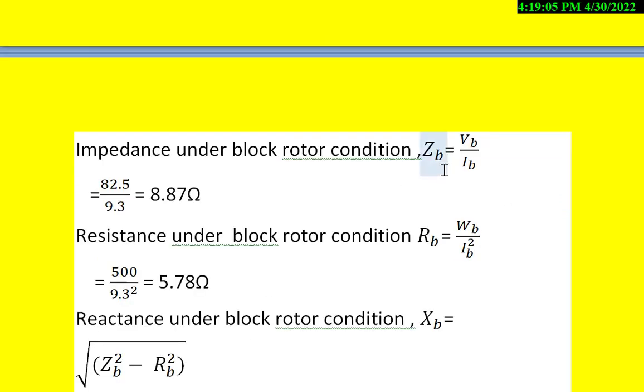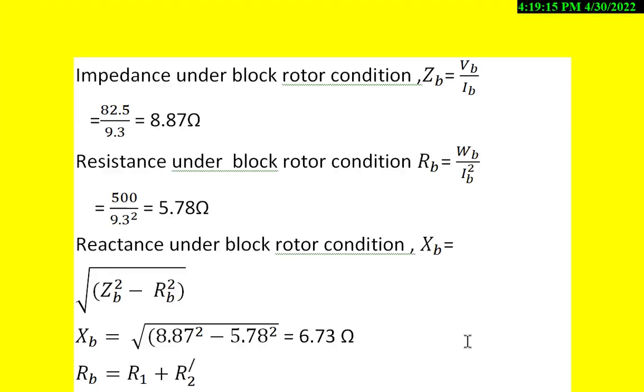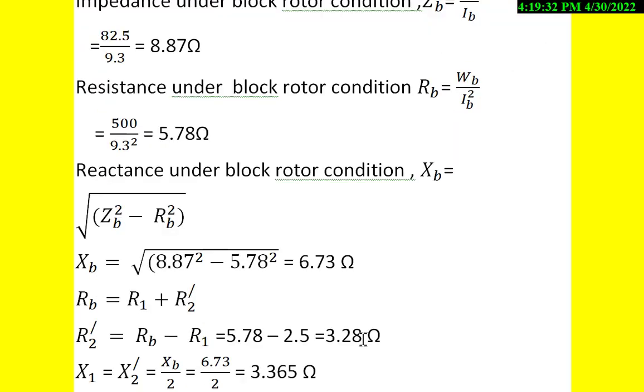Since ZB and RB are known, we can calculate the reactance under blocked rotor condition. XB = √(ZB² - RB²) = √(8.87² - 5.78²) = 6.73Ω.